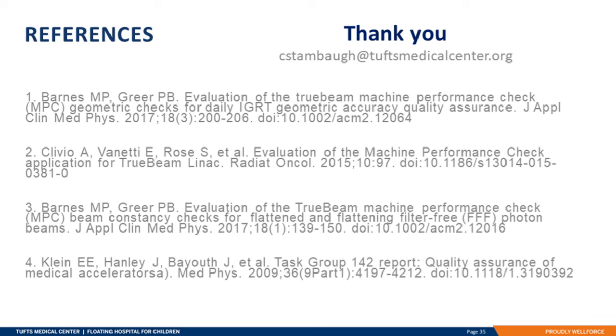Question number 2, can you give a little more detail on how the daily QA would occasionally double in time? Sure. So we had issues with machine performance check a few times where it wouldn't just fail, it would not record any results. We would run through the whole check and nothing would populate in the results section. And so sometimes it took 2 or 3 times of running it to actually get results to record. So that was one issue. And we also found that, since this was all retrospective, our therapists would occasionally take long breaks that were hard to figure out when they were happening while they were doing QA, whether it was to help at a different machine or if there was an issue somewhere else. So that was also part of it, but it didn't happen very frequently.